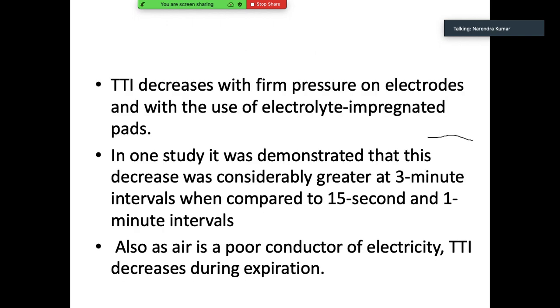Okay, and we should understand that the transthoracic impedance will also depend on the pressure. For example, if you have just put on the pads, one is a gel pad, and the other is a manual one where you are trying to apply firm pressure. The one with firm pressure, of course, will have a much lower transthoracic impedance. I hope everyone is aware, and they might also have been using those electrolyte-impregnated pads. That is the standard of care, I would say. They just put them with the gels on the chest, it's done, and they press the button.